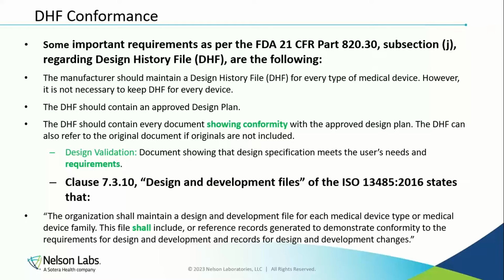You have to have a validation protocol established and in your design history file, not just signed by you, but signed by the facility that's performing the validation. You want to ensure that all of the factors that we talked about in the previous slide with the inputs and outputs, and how are they being verified, how are they being validated, are included in your file and your design validation protocol, right?